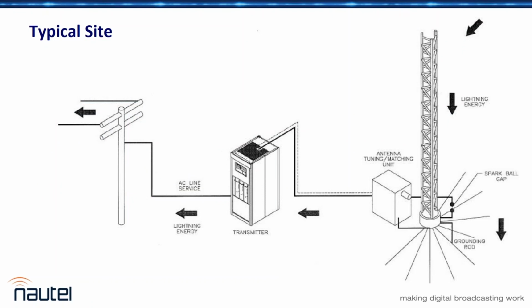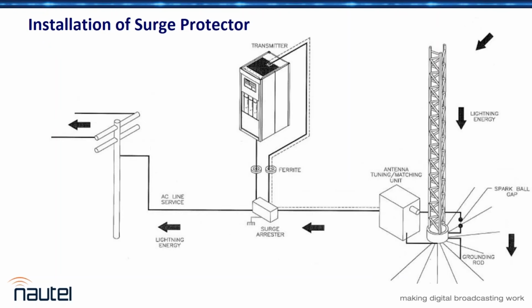This is fairly typical, and the goal really is to try to convert that to something like this. This is where the ferrites, in conjunction with a well-installed surge protector and a good single point ground system, go a long way toward basically removing the transmitter from the equation, or making it a much higher impedance to lightning energy.